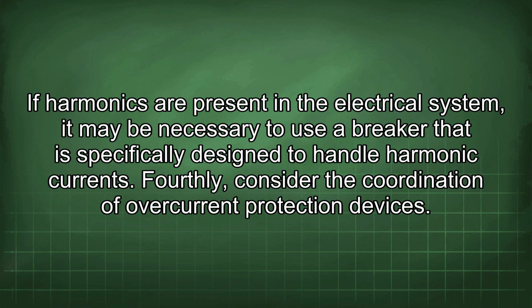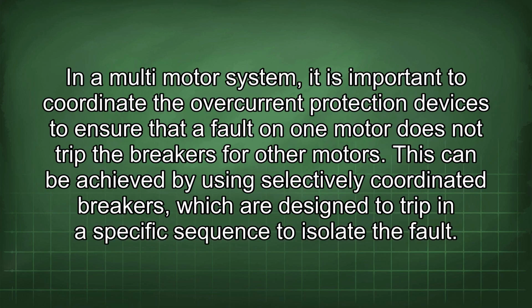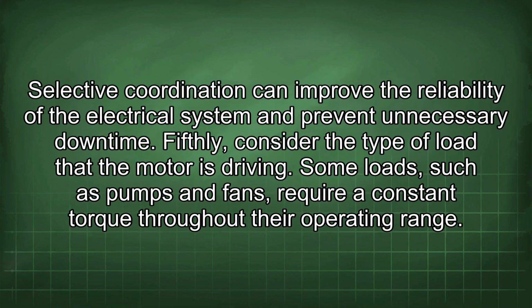Fourthly, consider the coordination of overcurrent protection devices. In a multi-motor system, it is important to coordinate the overcurrent protection devices to ensure that a fault on one motor does not trip the breakers for other motors. This can be achieved by using selectively coordinated breakers, which are designed to trip in a specific sequence to isolate the fault. Selective coordination can improve the reliability of the electrical system and prevent unnecessary downtime.